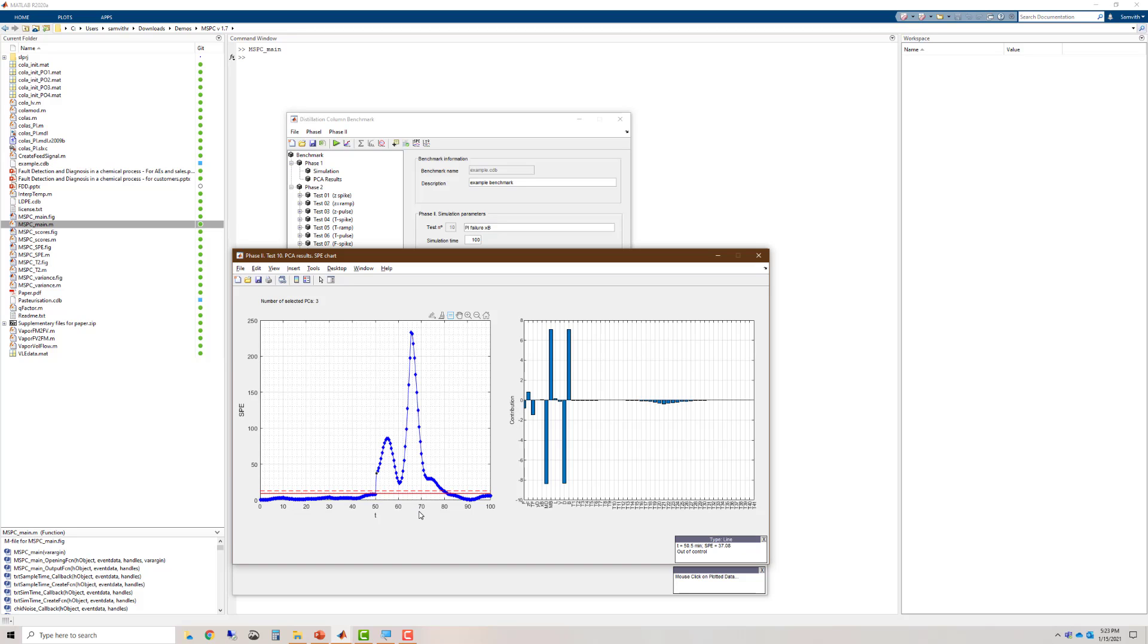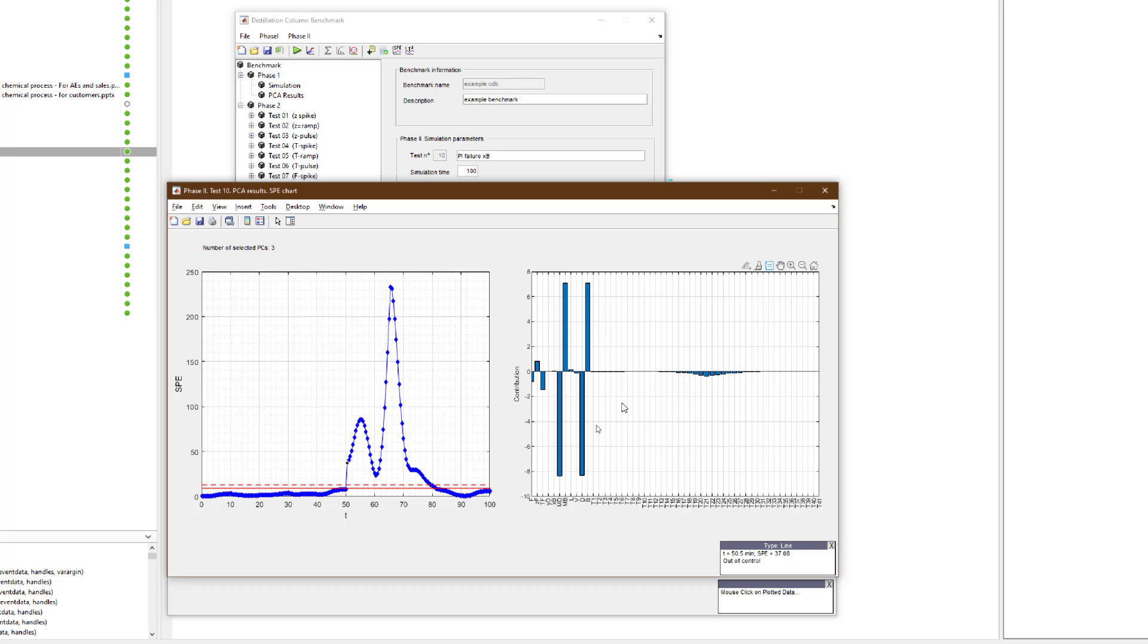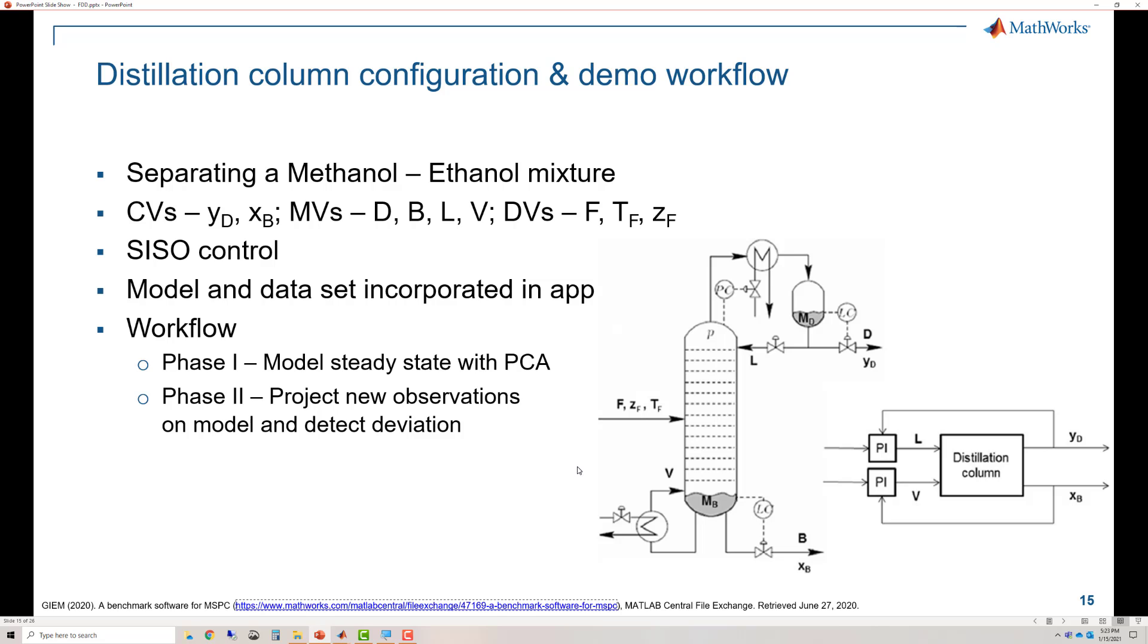Looking at the SPE chart, we see a relatively irregular pattern and a sustained fault. Clicking on the first point to get the contribution plot, we see that the variables contributing positively to the plot are MB and B. Going back to the process flow diagram, we see that MB and B are correlated due to the PI control loop. Thus, using your process knowledge, you should be able to figure out that there is a failure in the PI loop.